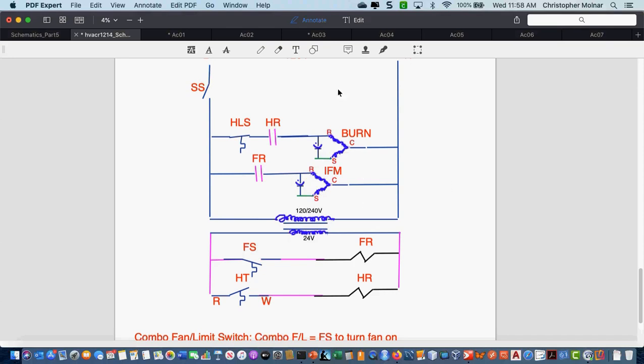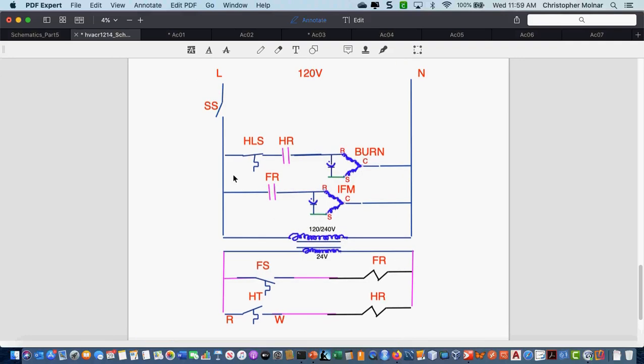Okay. This is, again, we now have our safeties in, we have our fan switch in, and I could draw this in different places, by the way. Tomorrow I'll show you another diagram with this drawn in a slightly different place. The fan switch can actually, I could not have a fan relay, and I could put the fan switch up here as well. You see it a lot of times just on the line voltage where I have the thermostat up here, and it's actually connected to the high limit in a way. It's called a combo fan switch that you can do both as line voltage. But this just happened to be one way you can draw it.